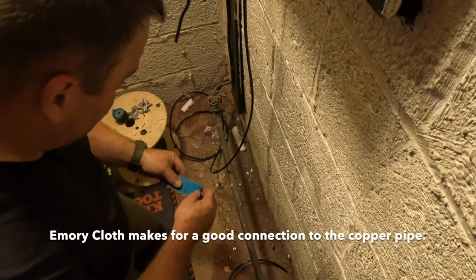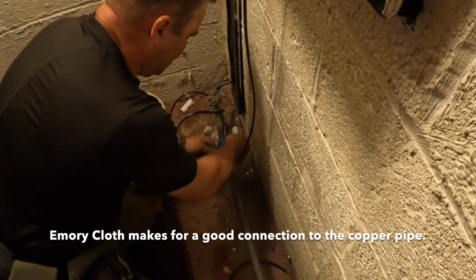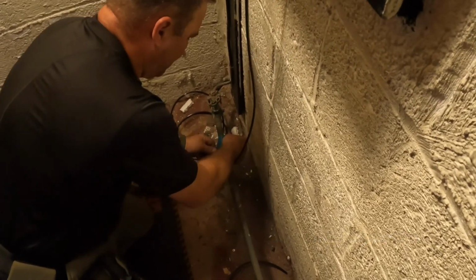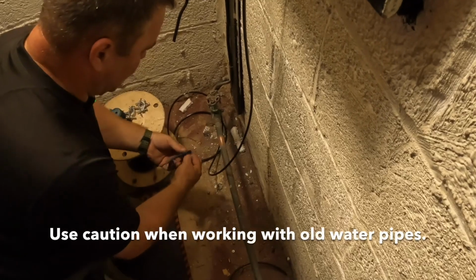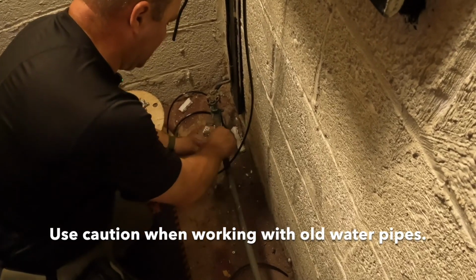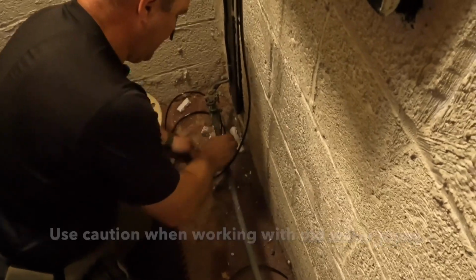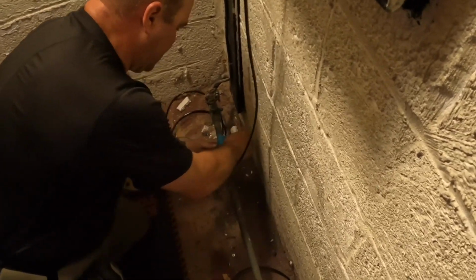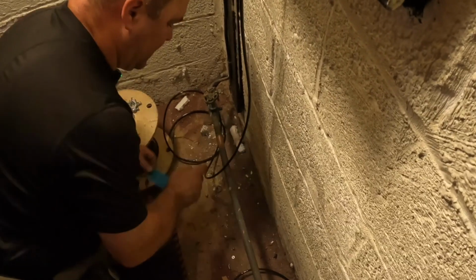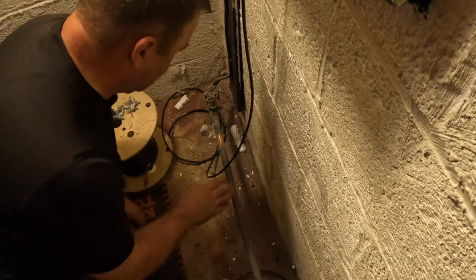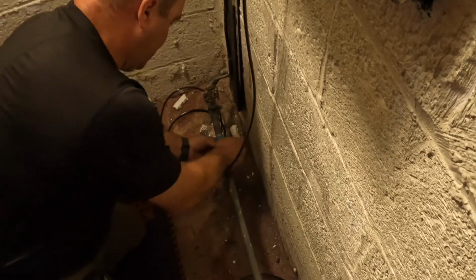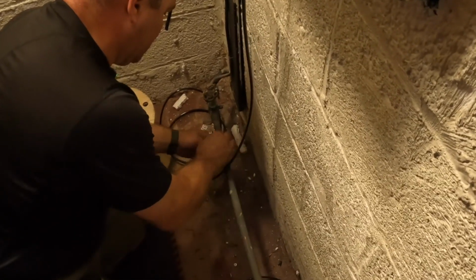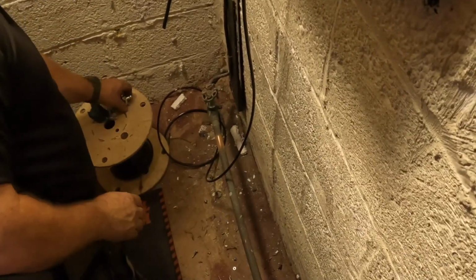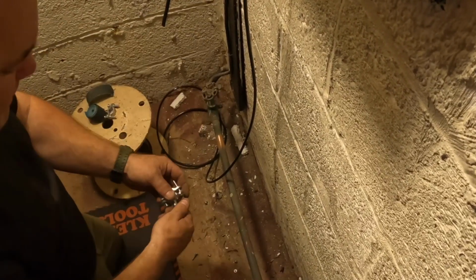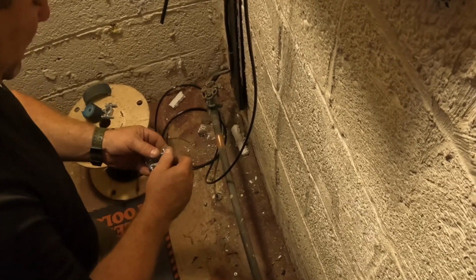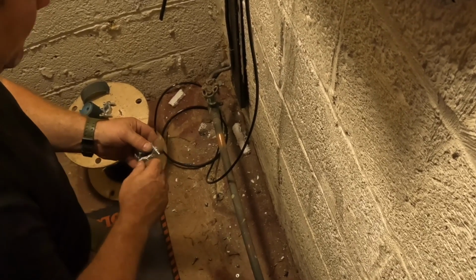Take a small piece like this and you rub off everything on that pipe so you can expose it to the bare copper. Plumbers know what this is, obviously. I feel kind of bad. The last couple ones I've done, they weren't as corroded, not corroded, but they weren't as colored as this one. So I got away with not doing it, but it's important to do it, so that my dual rated aluminum copper water ground clamp here gets a nice good bite onto the copper.